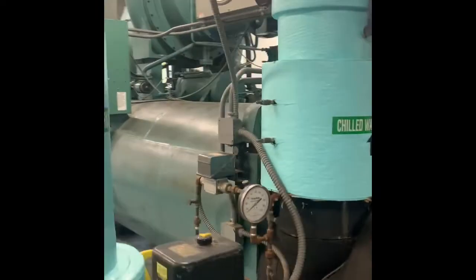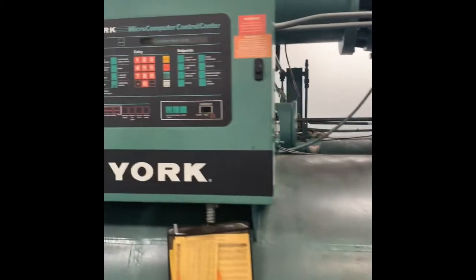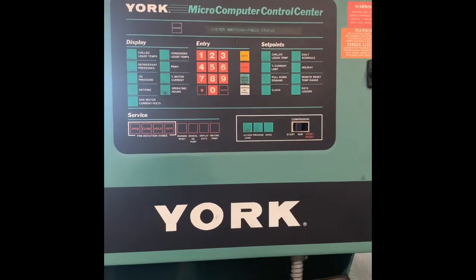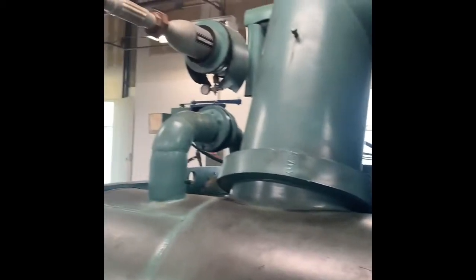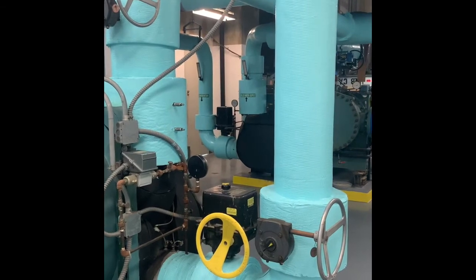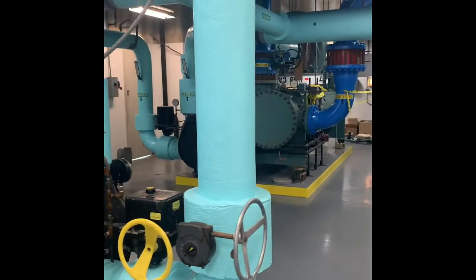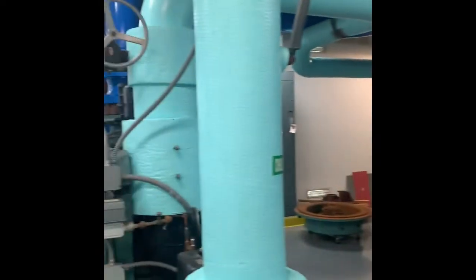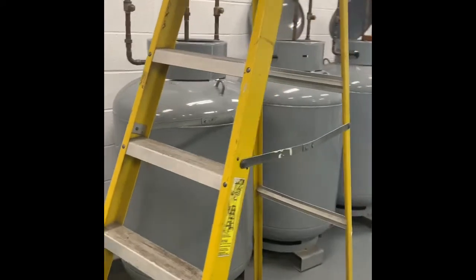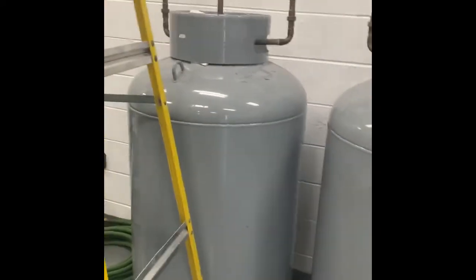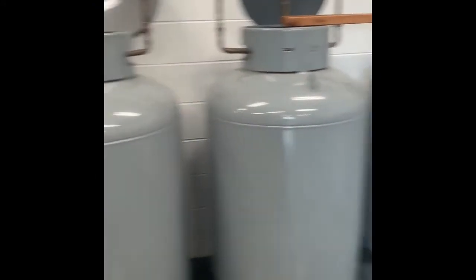So these are both 650-ton York YK low pressure. So they operate in a vacuum. We're using R11. Never really converted. This building was built and all this equipment was installed, what, '89, '90. So that was right around when the EPA was railing against refrigerants, and that's when R11 started to go by the wayside. But what we decided to do, since our equipment was so brand new, rather than retrofit, we said, hey, let's buy a ton and store it. So each one of these containers holds 1,000 pounds of R11. So that's 4,000 pounds, plus each machine holds about 850 pounds. So I've got enough R11 here to last a lifetime.